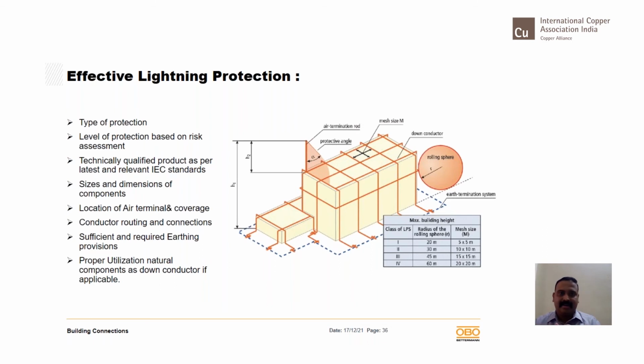When you ride a bike, if you are concerned about your hairstyle, obviously a helmet is a hindrance. But if you wear the helmet, it is going to save you. In the same way, relocating a lightning terminal for an aesthetic purpose should be kept as a secondary option, unless you can't avoid it, in which case you have to do it. Otherwise, preference should be given to the safety aspect. Then conductor routing and connections. There should not be multiple connections. The conductor routing should be as clear and as short as possible. There should not be multiple conductors connected together.